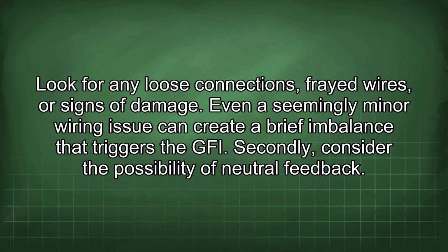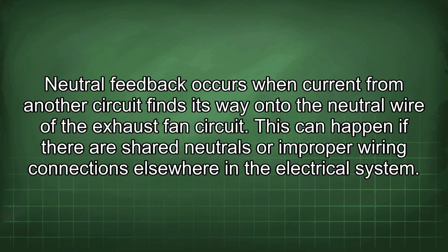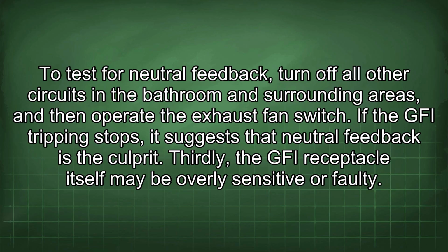Secondly, consider the possibility of neutral feedback. Neutral feedback occurs when current from another circuit finds its way onto the neutral wire of the exhaust fan circuit. This can happen if there are shared neutrals or improper wiring connections elsewhere in the electrical system. To test for neutral feedback, turn off all other circuits in the bathroom and surrounding areas, and then operate the exhaust fan switch. If the GFI tripping stops, it suggests that neutral feedback is the culprit.